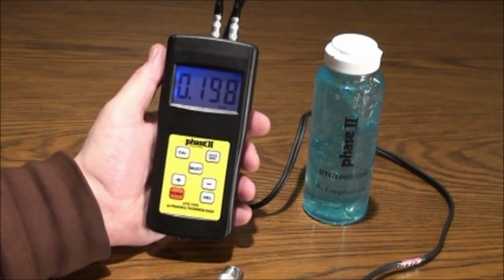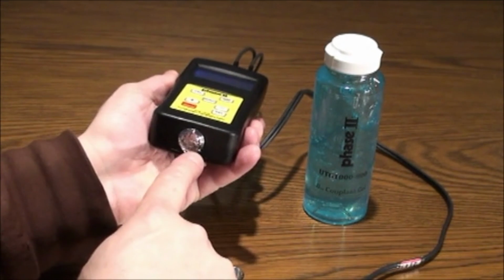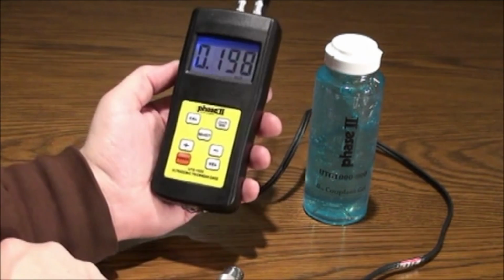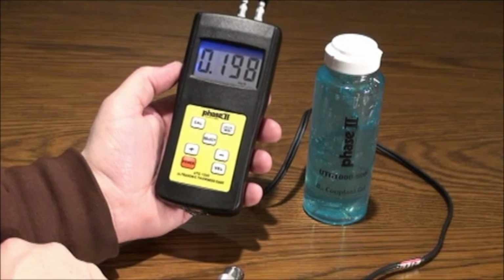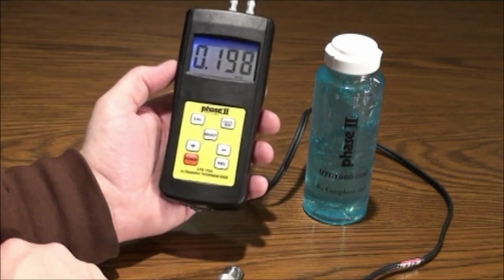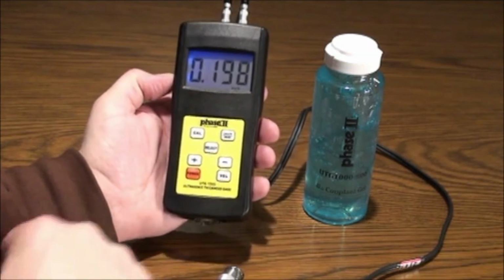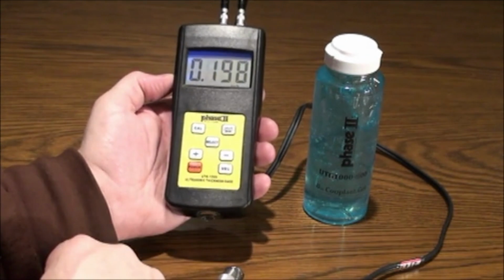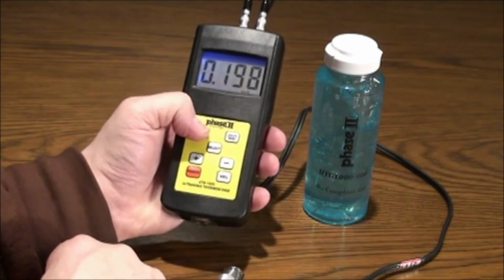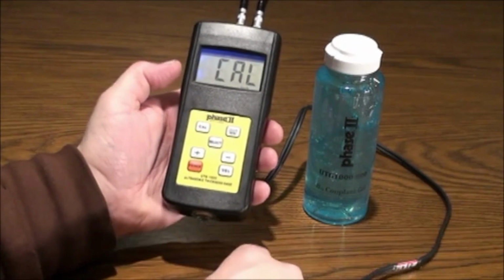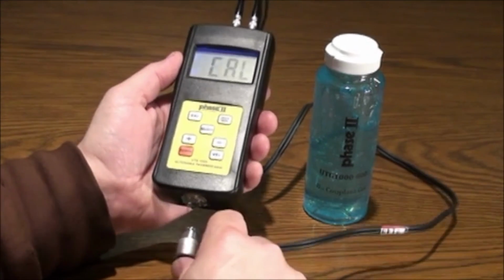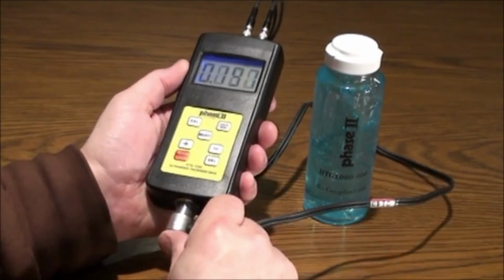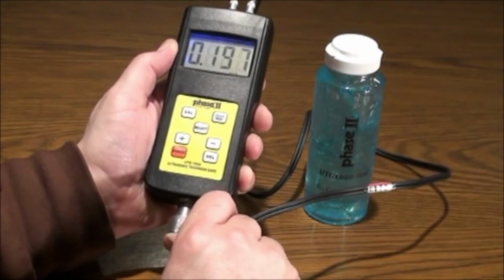The gauge has a built-in calibration block on the bottom surface of the gauge. The thickness of this block is 5 mm or 197 thousandths. Place a small drop of coupling gel on the calibration block. Press the calibration key and Cal will flash on the display. Press the probe flat on the calibration block, making sure the coupling indicator appears on the display.